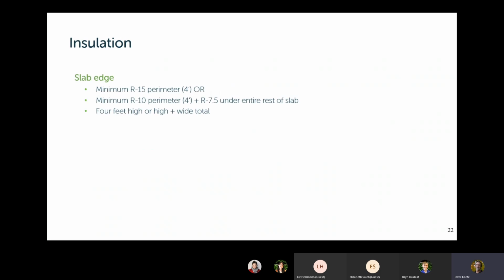For slab edge, this applies to basically slab on grade. The code talks about slabs that are at grade, above grade, or within 1 foot of grade. So this does not apply to the slab in a deep basement, for instance. So if you have a slab that's at or near grade, it's an R15 perimeter insulation, or R10 perimeter plus R7.5 under the rest of the slab.